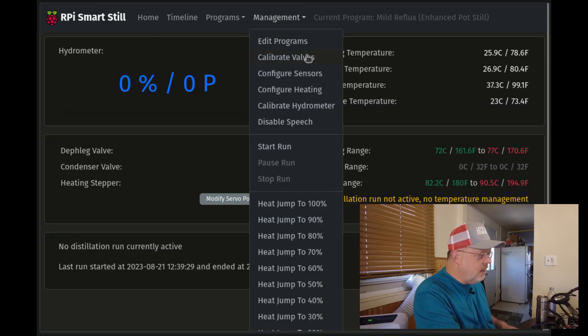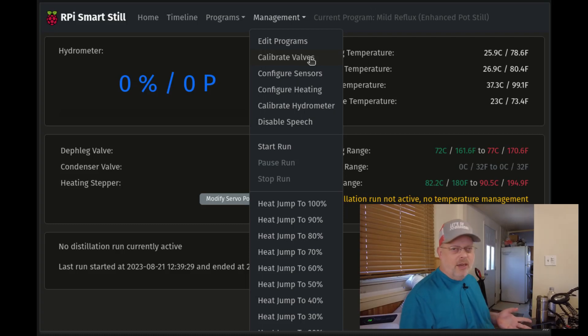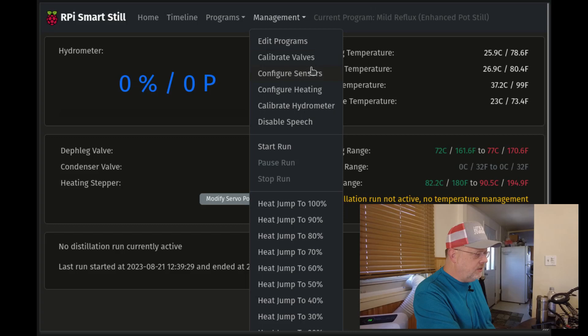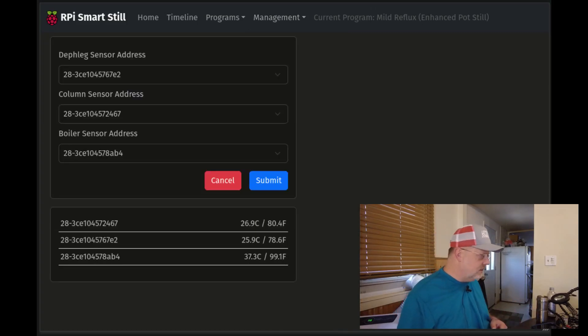Back in the Management menu: Calibrate Valves — you only want to do this when your water lines are pressurized. What this does is open and close your cooling valves for your dephleg and condenser and times them, so it knows how many pulses there are from full closed to full open and back. I always do it twice in a row to make sure there's no air in the water lines that could affect the motion of the ball valve.